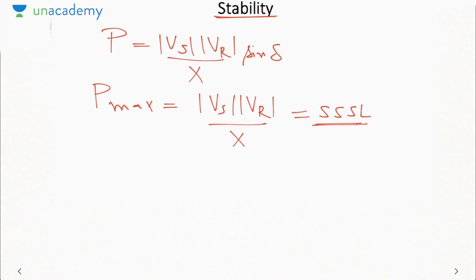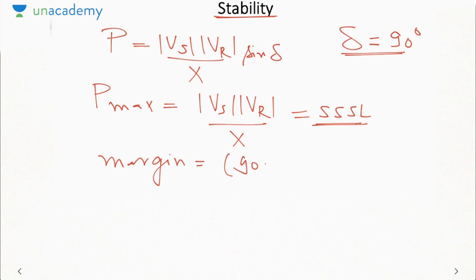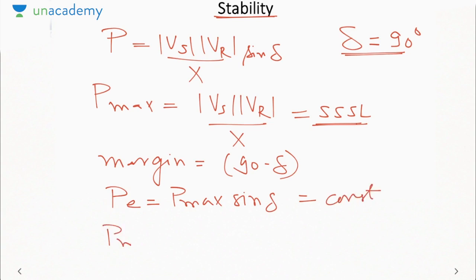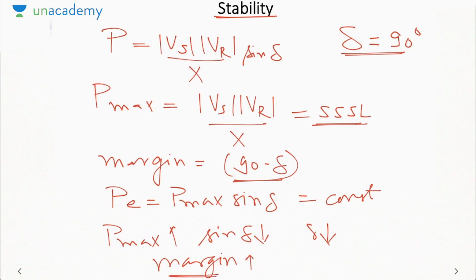How? First of all, since delta is equal to 90 is the stability limit, so you must stay as far as possible from delta equal to 90. So we can define a stability margin as 90 minus delta. Now electrical power will be P max sine delta. Suppose this remains constant as the load is constant. So as we increase P max, sine delta should reduce, or we can say delta must reduce, due to which this margin will increase. Okay, if margin increases, that means I am making the system more stable. So that is how, if we increase P max somehow, then the stability should improve.